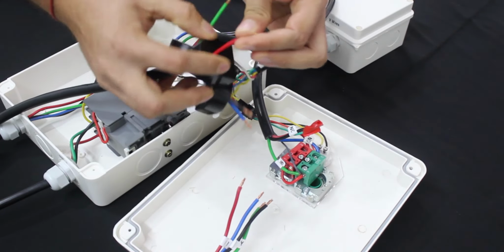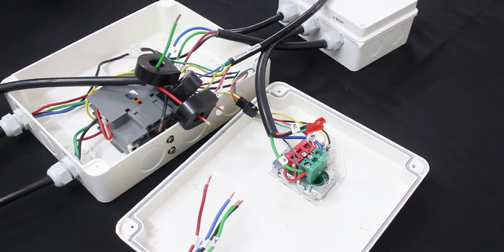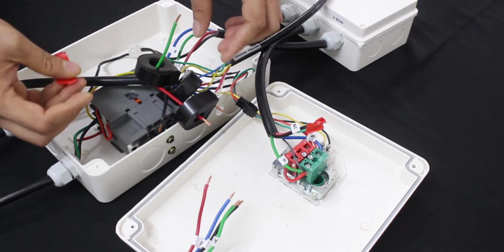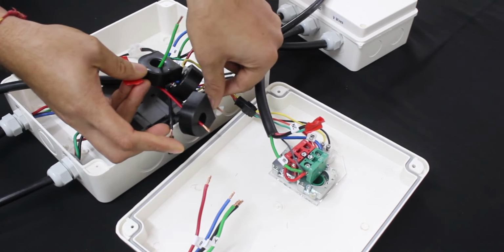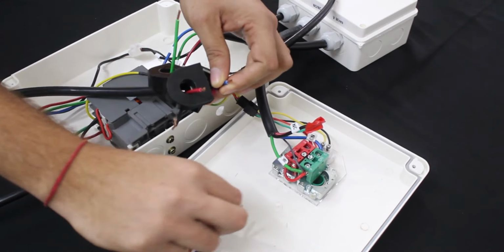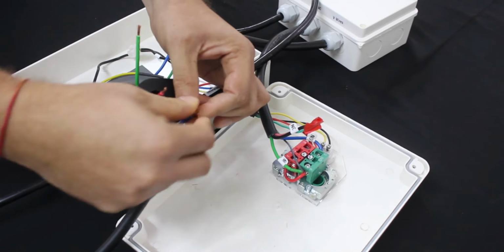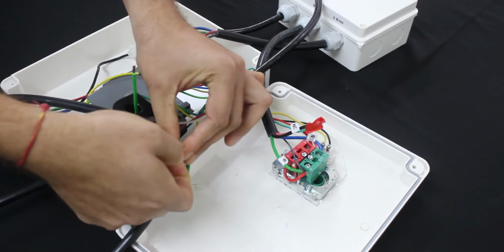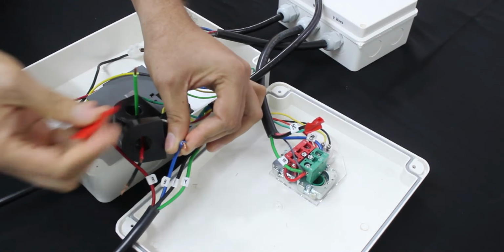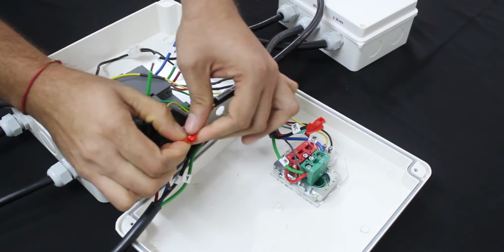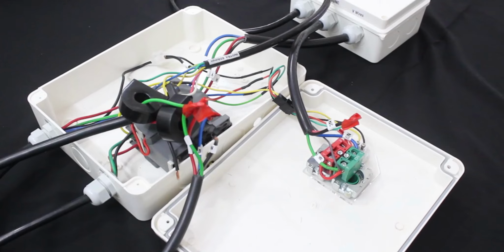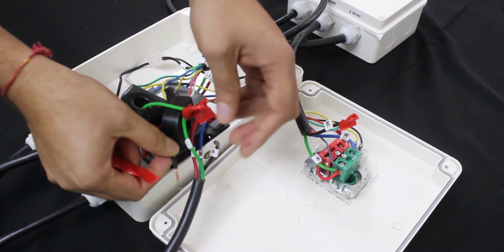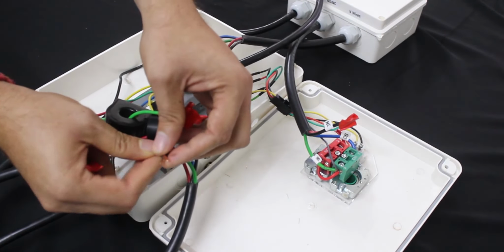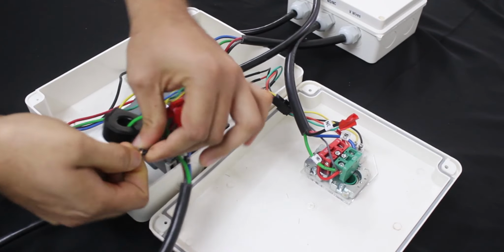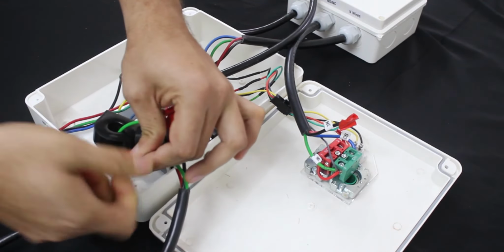Now connect the wires from the CT to the output wires of the motor panel. Take the blue wire from the CT and connect it to the blue wire of the motor panel with an insulation tape. Do the same for red and green wire. Now connect the neutral wire with the neutral wire present in the motor panel and wrap it with an insulation tape.